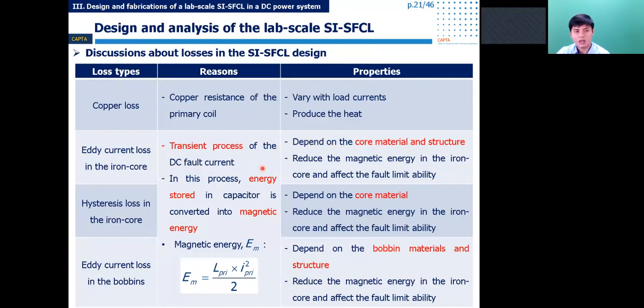In the practical design of the SI-SFCL, the loss is a very important factor. It can reduce the magnetic energy during the transient fault, thereby reducing the inductance as well as the fault limiting capability of the SI-SFCL. There are three main losses in the SI-SFCL, including the copper loss in the primary coil, the iron core loss, and the eddy current loss in the coil bobbins. So next, I will design the iron core and the coil system based on the loss and the material cost problem.